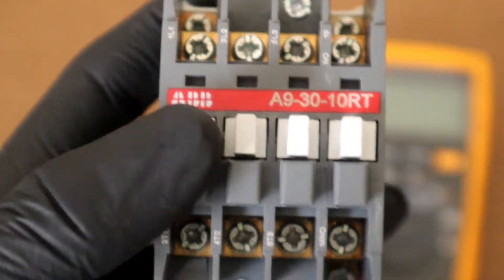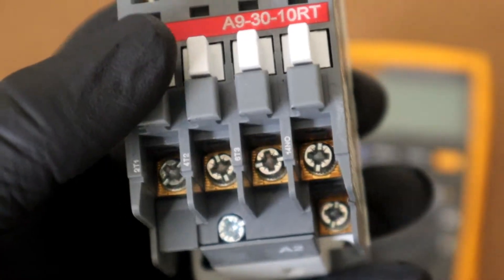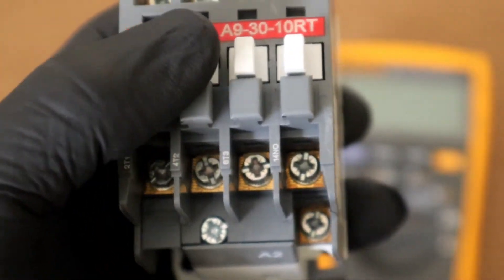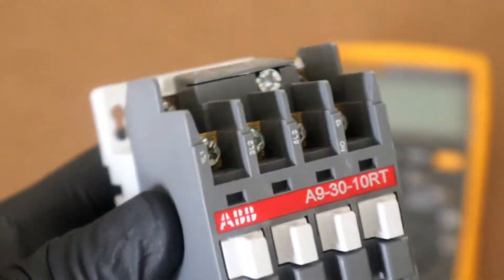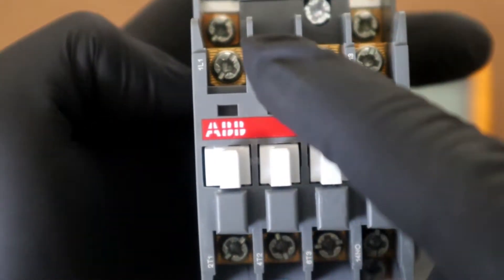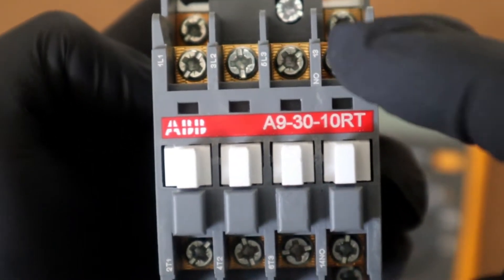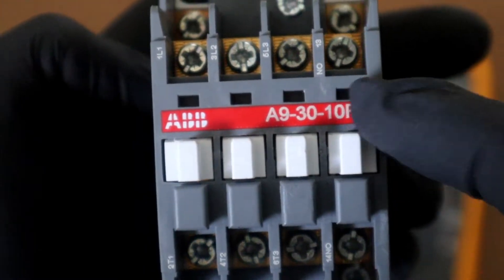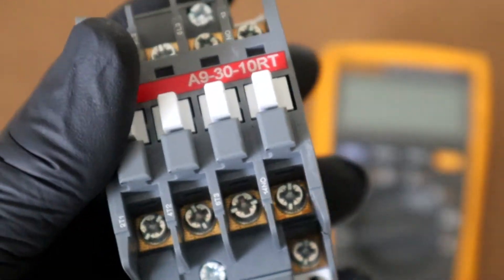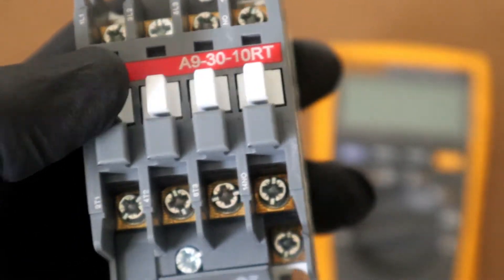In testing a contactor, high ohms nearing infinity when the contactor is open. In its normal state when it's open, if we test across L1 to T1 or L2 to T2 or L3 to T3 or across our normally open contact we should have a very high resistance reading or an open line resistance reading.